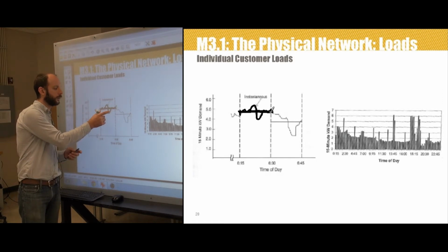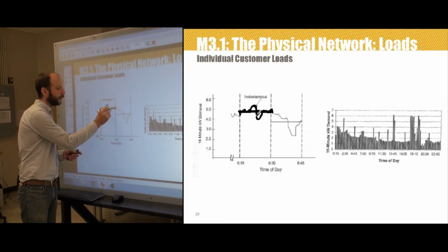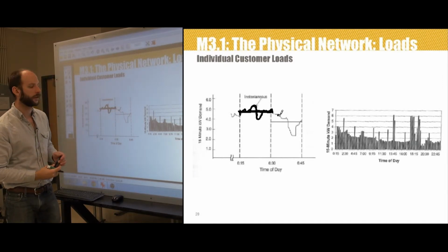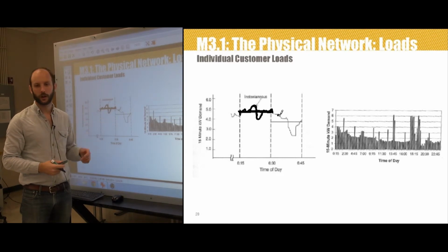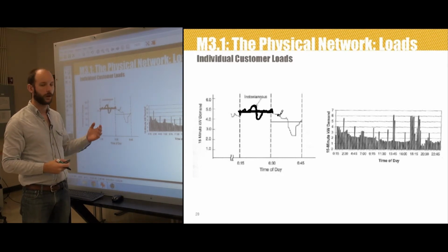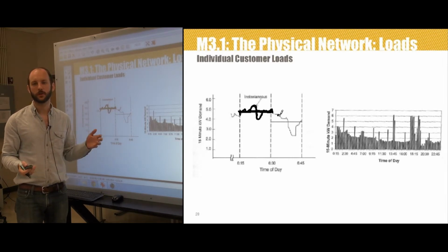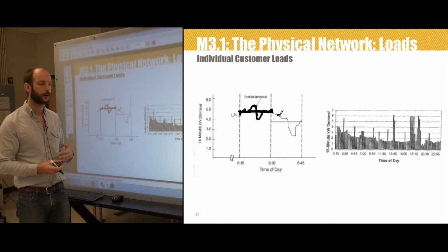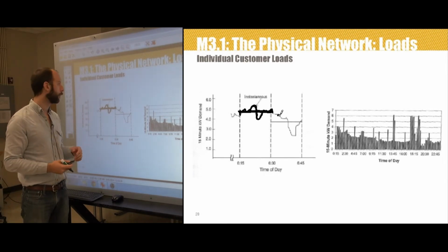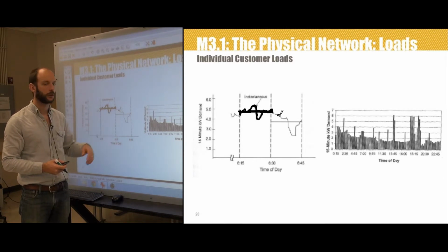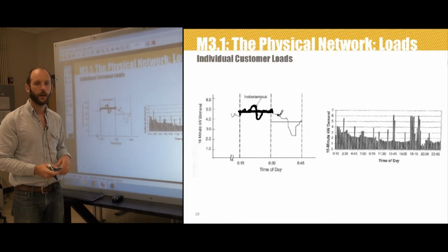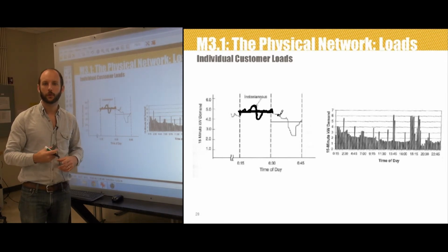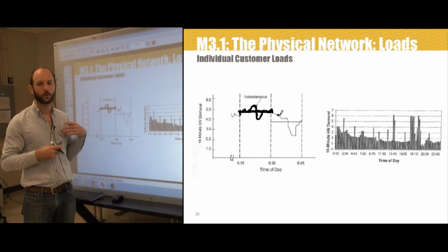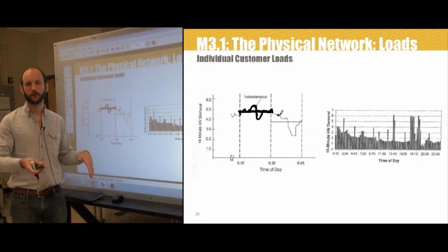You might say, well, why don't I just take the exact load value or demand value at any given point? Why don't I just use that information? Why am I even averaging it? Well, historically it's been very difficult to collect that kind of information from customers. Think about your electric utility. They actually only measure how much energy you used, and they measure that data point once a month when they read your meter. So even getting 15-minute intervals from all the customers in the electric utility industry has been relatively difficult. And also smaller intervals require more complex and expensive data acquisition tools, so we're going in that direction in the electric system with smart grids and smart meters.